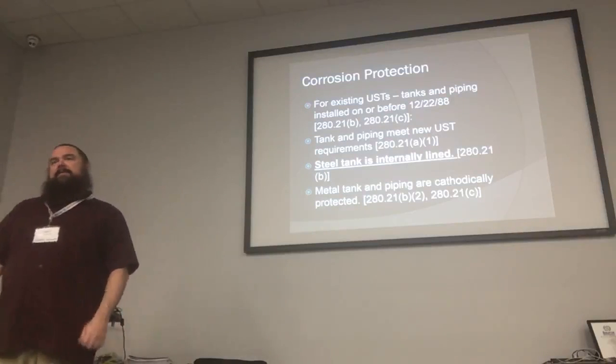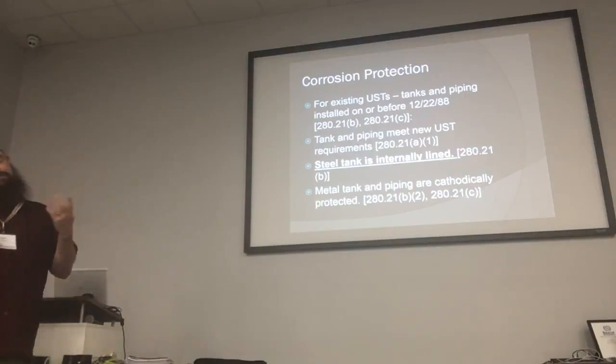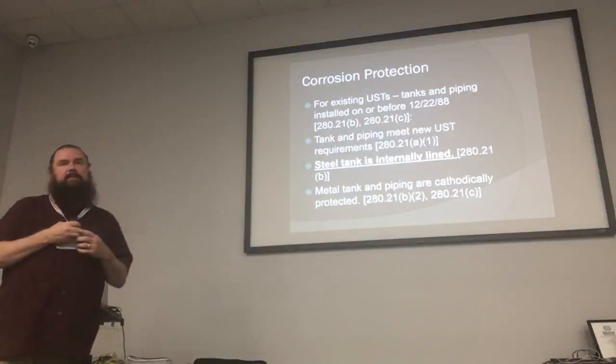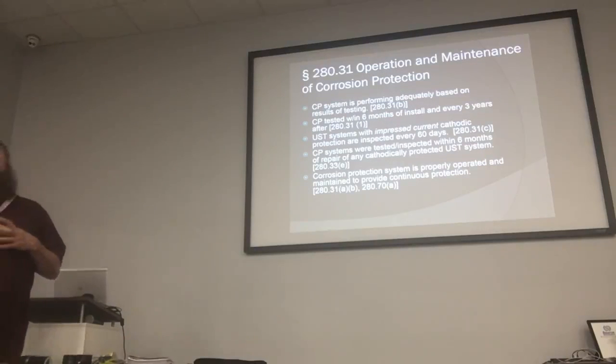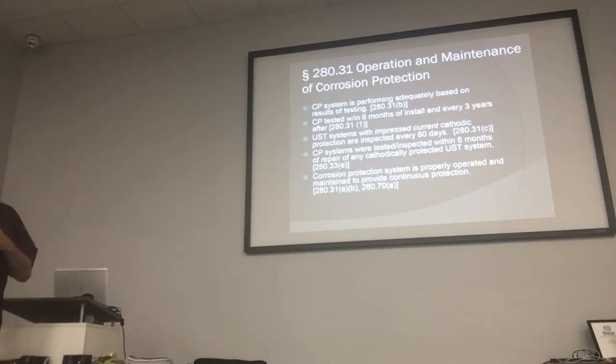If you have existing tanks or piping installed before 1988 — which we're not going to talk a lot about, because they're so old — you had to make sure they're cathodically protected, that they meet the new UST requirements, that any steel tank is internally lined, and that the metal tank and piping are cathodically protected. The CP system has to be performing adequately and tested to make sure it is.